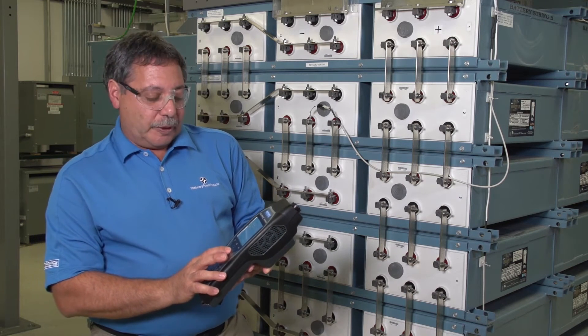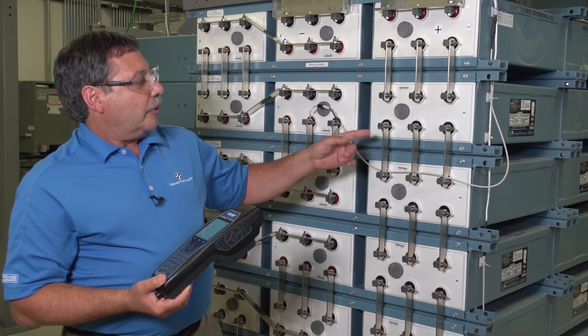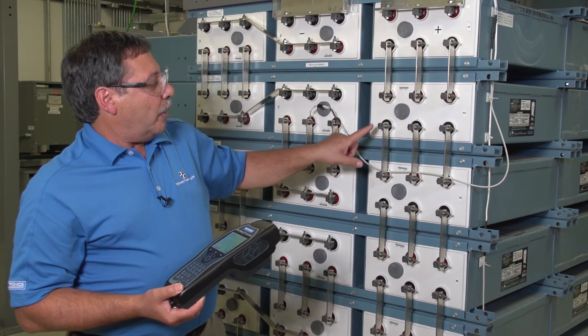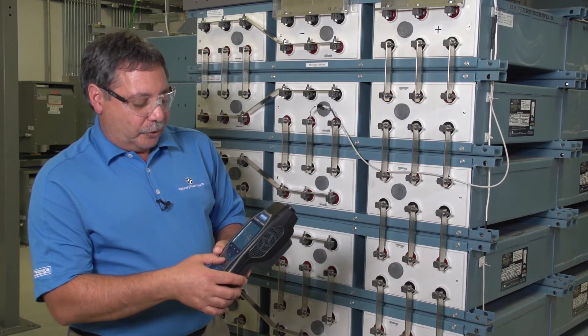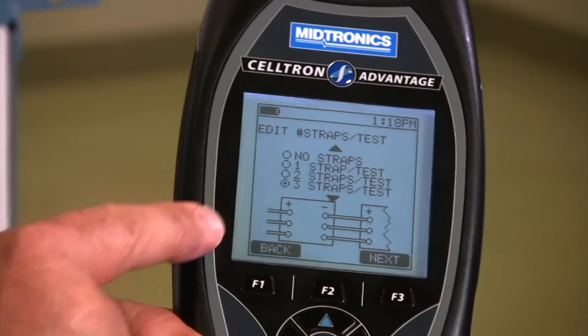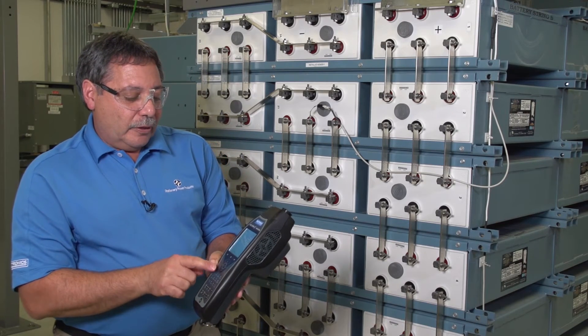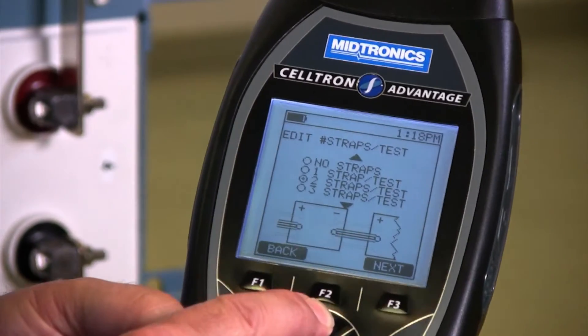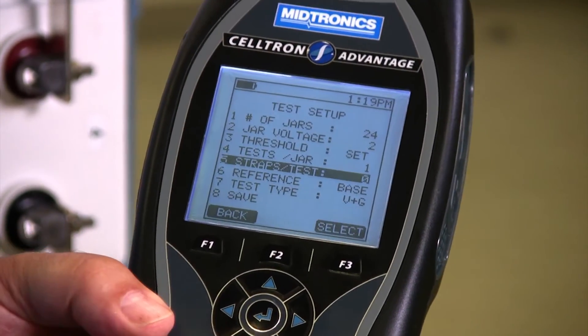Next is what we call the strap test, which refers to our intercell connectors. So if I wanted to do one test across this cell for the battery test, but wanted to test each intercell connection here, I could set this up to do three strap tests and it'll give you a picture of just that setup that matches our configuration here in our battery stack. If you had to do those strap tests, you can set it up. If your policy is no strap test, you just leave it at none.